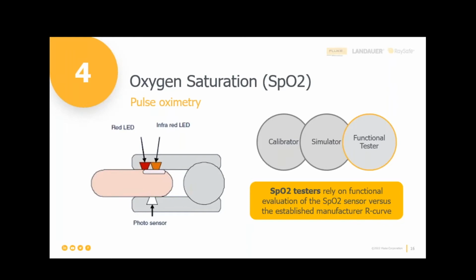But the forehead is a special measurement that we would like to use more in trauma, and anytime we have a problem with the perfusion of the blood or peripheral vascular shutdown, right? Because the vessel here in the forehead stays open longer. Why? Physiologically, to feed the brain, make sure the brain has oxygen, even if other parts of the body don't. But that uses reflectance sensors. So it's bouncing a light signal off the tissue. We're still looking for pulsation in order for us to assess that. But those are the two different types of sensors.